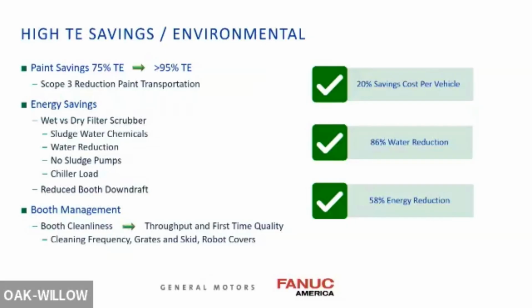And another thing to think about is the utility load on the paint shop's chiller system and hot water generator system that you have with the wet scrubber versus dry filter. The air leaving the wet scrubber is close to 99% relative humidity. You've just washed that air with water. All that moisture is brought up to the booth recirculation air supply house, to the cooling coil, where all that moisture has to be condensed out of the airstream. Only to a few feet later, downstream, it hits the reheat coil to bring that air back up into the booth temperature and humidity set point. It's extremely inefficient. So on top of the improvement to the utilities, with the reduced downdraft, you can reduce the horsepower motors of your fans in your air supply house. When you add it all up, you'll see a 58% reduction in your booth energy usage.